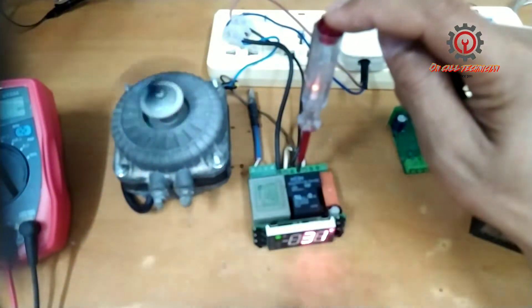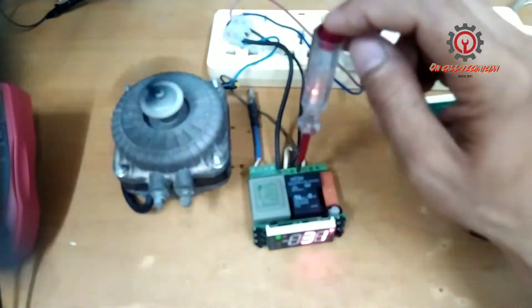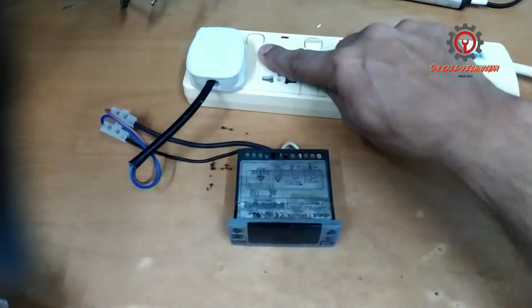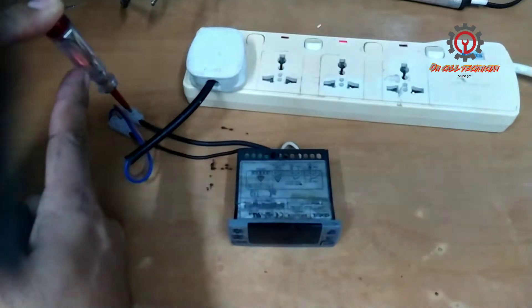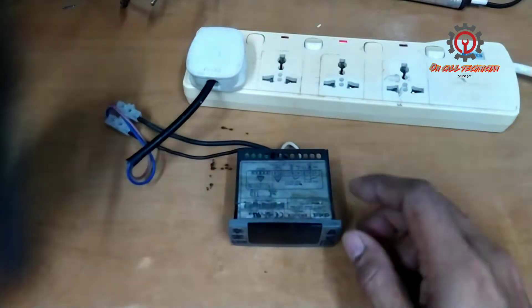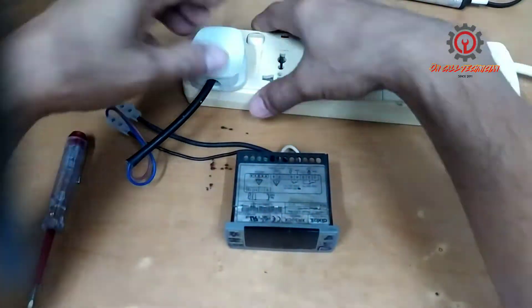Welcome once again guys to my YouTube channel. Today's topic is how to fix the Dixell XR30CX, and the issue is dead set or no power. It's already powered on and here is our line — my test pen lights up but this control doesn't power on. We're going to check it.